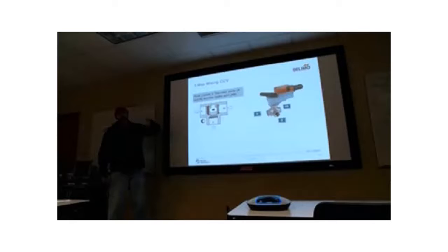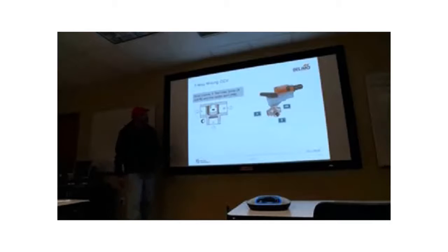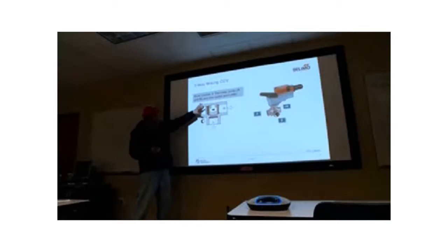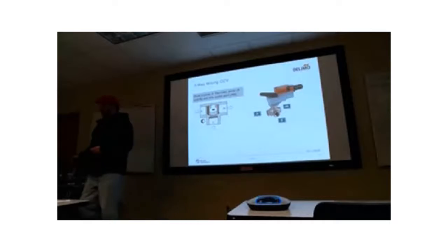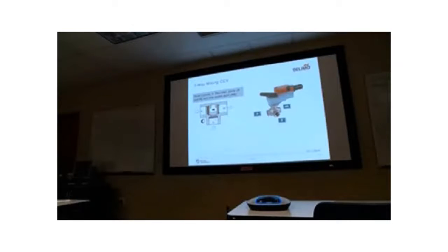So three-way valves are either throughout the whole system. That's what we call Stone Age technology, like 70s technology. Or more likely what you see today is two-way valves in most of the building, and selected coils that have three-way valves, and that's to maintain that minimum pump flow. But anyway, here's what I want to get across here. This is a cutaway view of the characterized control valve that's right there. Notice here that it's a cutaway. There's 3 ports in it, right? Call it a T configuration, whatever you want to call it. Let me do this now in case we lose it later. I can emphasize it later, but I want to try to get it across now.